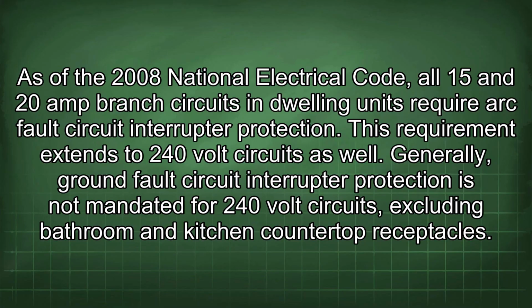As of the 2008 National Electrical Code, all 15 and 20 amp branch circuits in dwelling units require arc fault circuit interrupter protection. This requirement extends to 240 volt circuits as well. Generally, ground fault circuit interrupter protection is not mandated for 240 volt circuits, excluding bathroom and kitchen countertop receptacles.